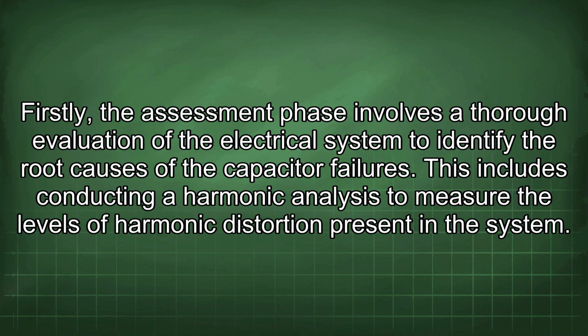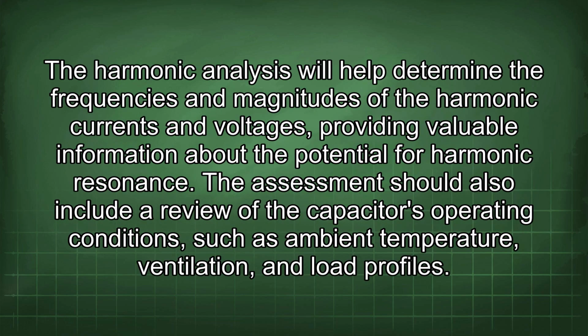failures. This includes conducting a harmonic analysis to measure the levels of harmonic distortion present in the system. The harmonic analysis will help determine the frequencies and magnitudes of the harmonic currents and voltages, providing valuable information about the potential for harmonic resonance.